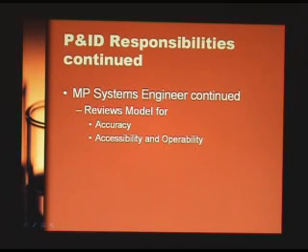So the process engineer, he or she, will review the models for accuracy, that some pipe that was intended to be 6-inch is not shown as 2-inch by mistake. Accessibility and operability. If you have done any model reviews, you will have had this little man, an imaginary little figure, walking around your model in cyberspace.